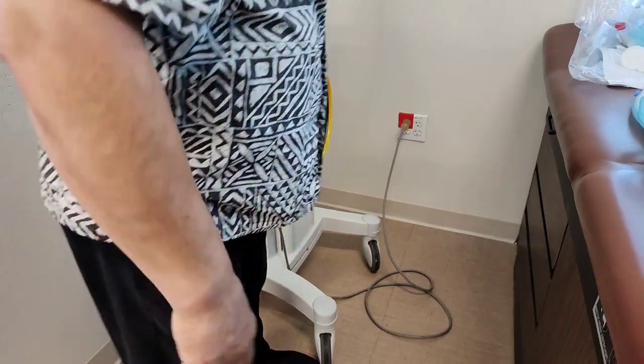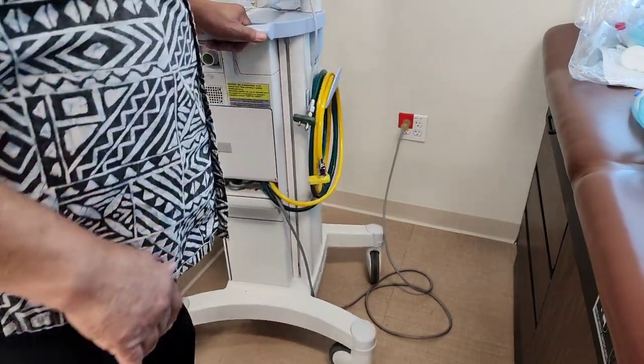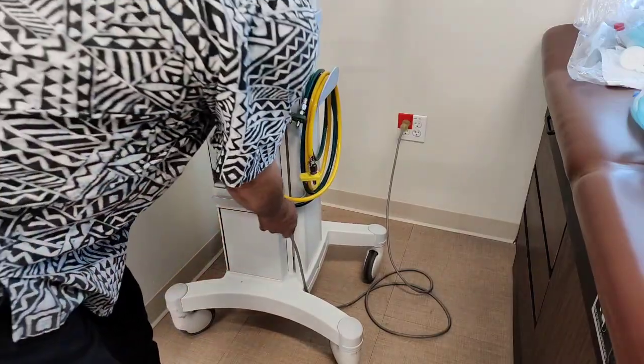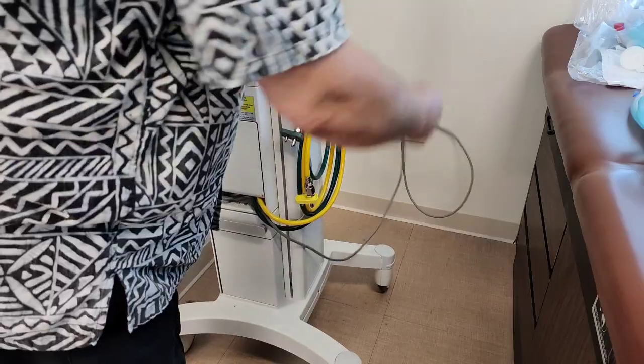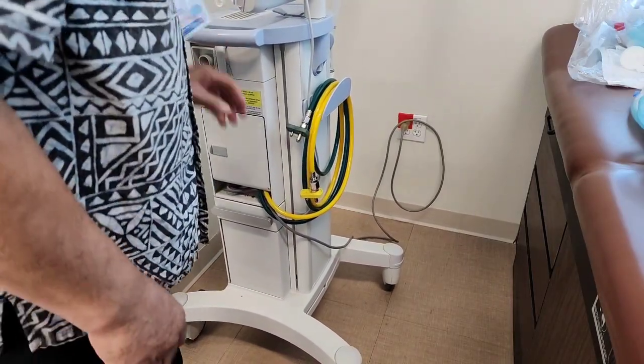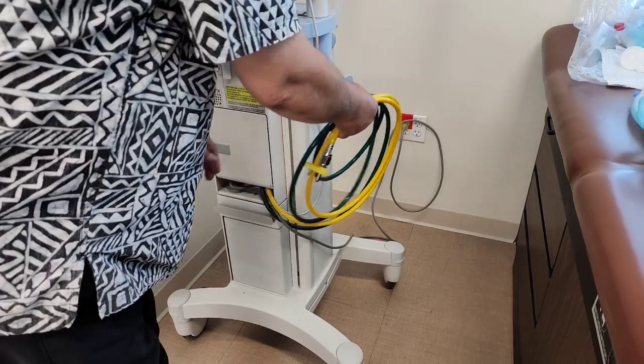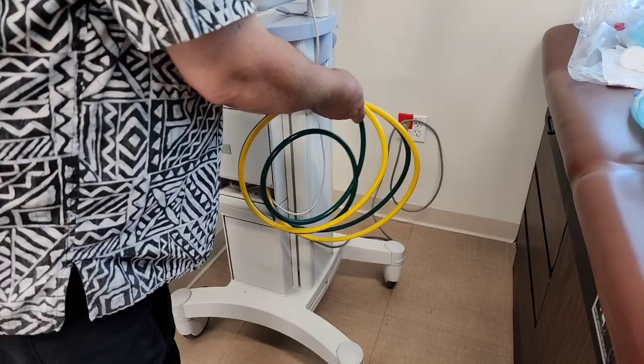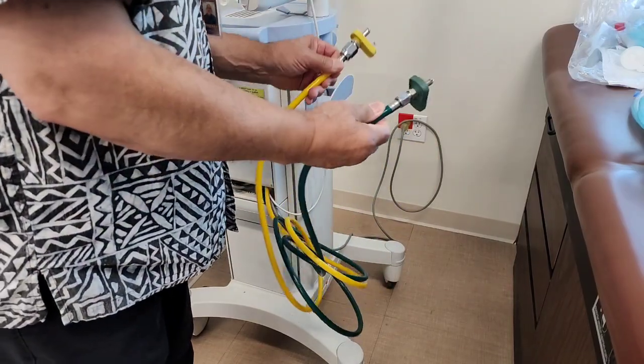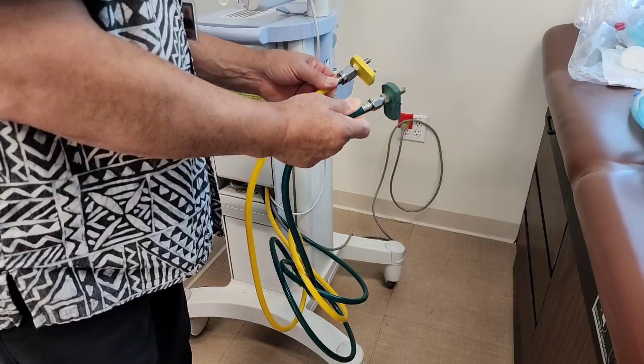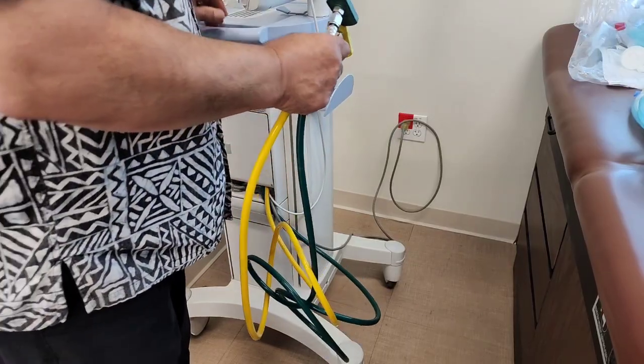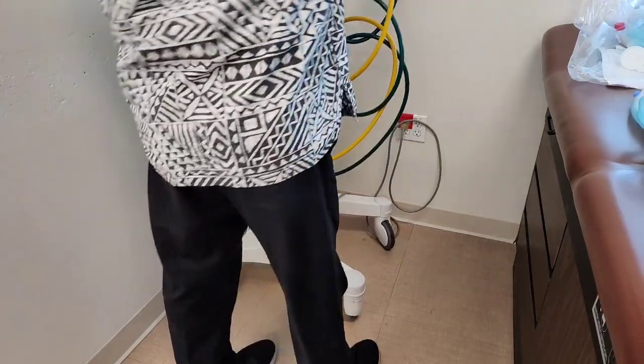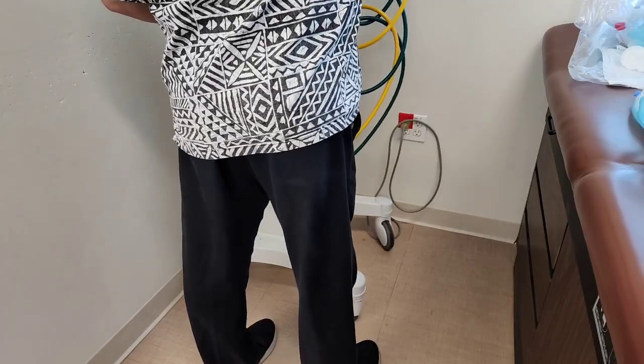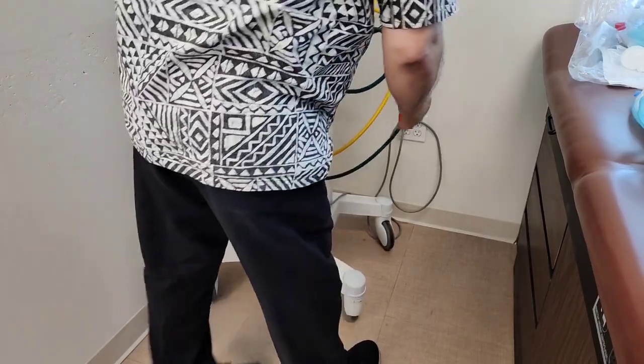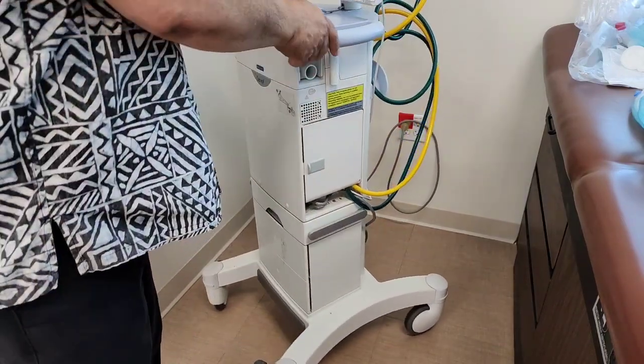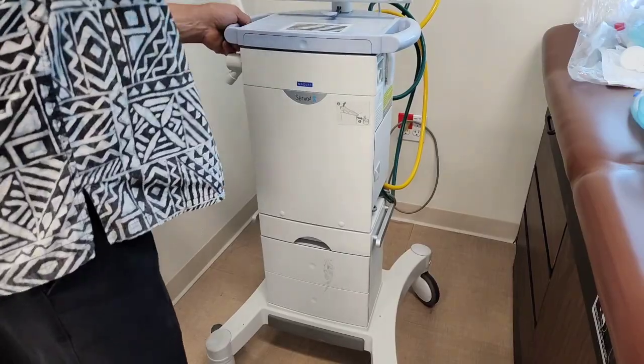And the backup generator kicks in. Ventilators or life support devices will be connected to that, and they will continue to operate as long as necessary. Then you'll have the pneumatic portion of it. You have your oxygen, your air. Those will be connected to the wall appropriately. This is your quick connects. Some might have a DISS connector, diameter index safety system type connectors.